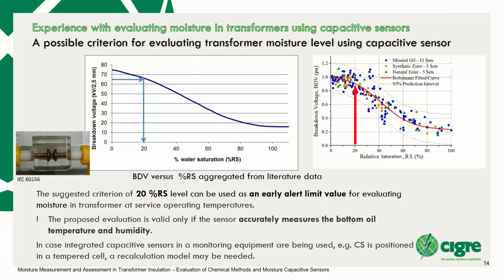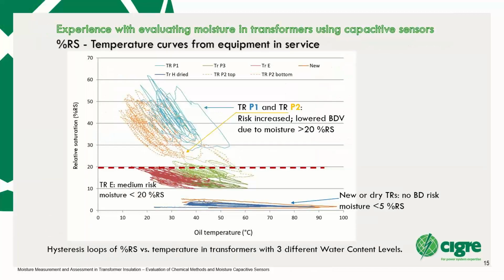Again, going back to our curve showing the dependence of breakdown voltage on water saturation. We can see here that in the case of capacitive sensors, we can have a kind of criterion which is acceptable. And this criterion is exactly these 20% which can be used for this purpose. On the next graph, I can show you a lot of graphs taken from real cases, which show that very clearly.